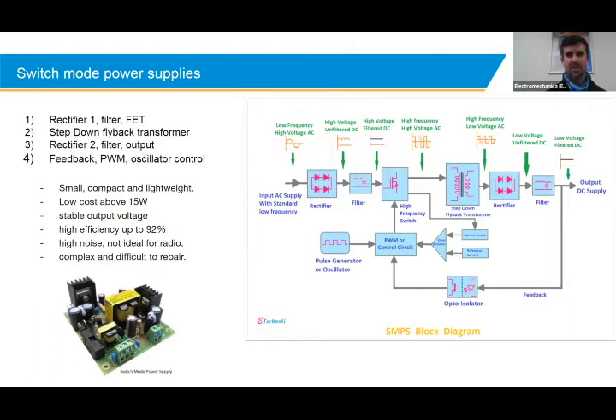Powers above 15 watts is very cost effective. I think your linear power supply might still be more cost effective below your 10 to 15 watt region, but anything above 15 watt, switch mode power supplies become much more attractive. Stable output voltage due to the feedback that is sent back to the controller. So if there's a dip in voltage due to perhaps a high load or an inrush, outrush current, the power supply can react by having this feedback system back into its control circuit to increase the output, to maintain a very steady 24 volt or 12 volt output. Compared to a linear power supply, which wouldn't have such feedback, it wouldn't be able to react in the same way that a switch mode does.